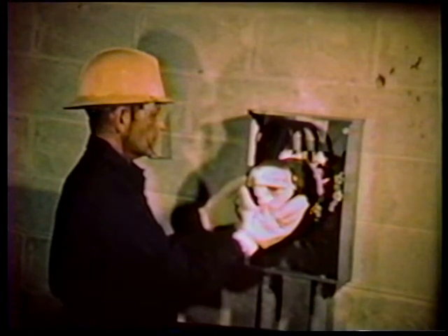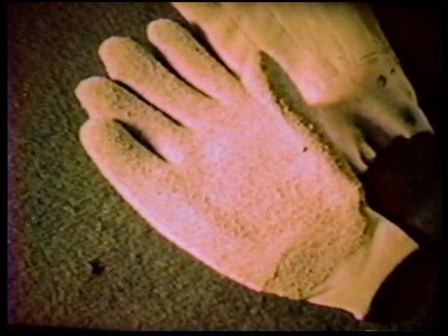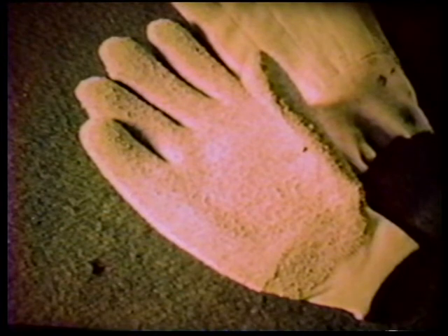Here's a good example of a situation where eye protection should be used. The meter glass is cracked. Notice the man also has on a pair of special cut-resistant gloves. These gloves protect the meterman's hands from cuts. Cut-resistant gloves should be used whenever working where glass is broken or might be broken. Here, the cracked glass has broken, but the meterman's hands are protected.